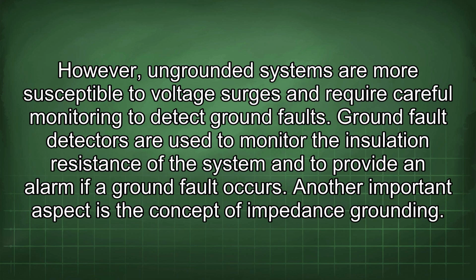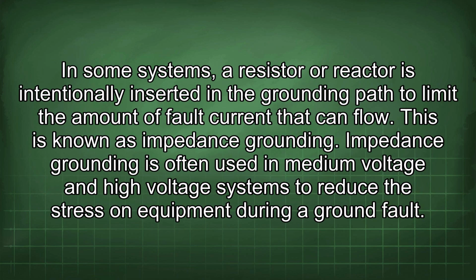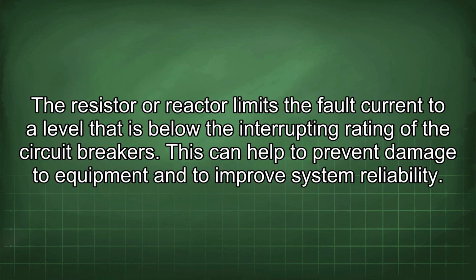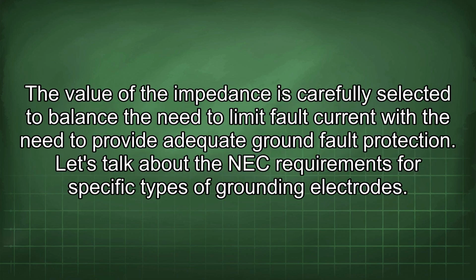Ground fault detectors are used to monitor the insulation resistance of the system and to provide an alarm if a ground fault occurs. Another important aspect is the concept of impedance grounding. In some systems, a resistor or reactor is intentionally inserted in the grounding path to limit the amount of fault current that can flow. This is known as impedance grounding. Impedance grounding is often used in medium voltage and high voltage systems to reduce the stress on equipment during a ground fault. The resistor or reactor limits the fault current to a level that is below the interrupting rating of the circuit breakers. This can help to prevent damage to equipment and to improve system reliability. The value of the impedance is carefully selected to balance the need to limit fault current with the need to provide adequate ground fault protection.